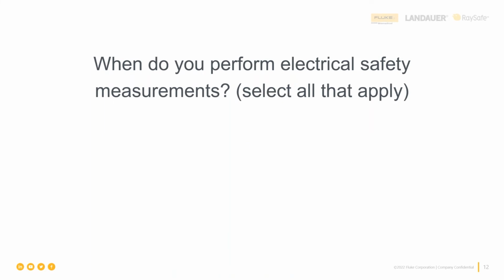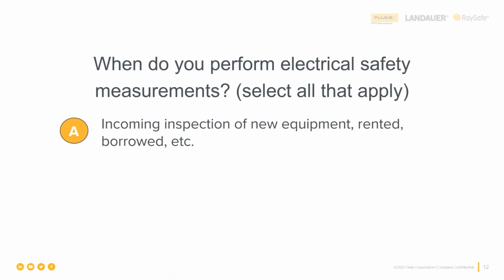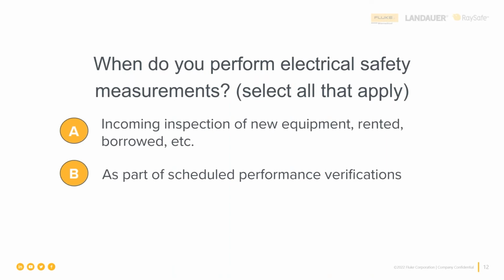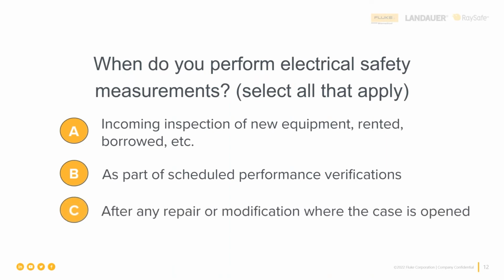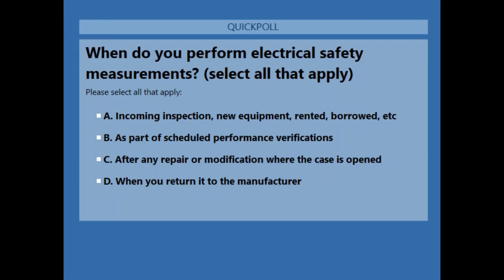So when do you perform electrical safety measurements? Now, electrical safety testing and electrical safety measurements may be different. We'll talk about that under NFPA 99. But when do you perform electrical safety measurements? Incoming inspection of new equipment, as part of scheduled performance verifications, or after any repair or modification where the chassis is opened. And this is multiple response, so you can pick more than one here. So please, Edna, launch this poll question. And that poll question has been launched, Jerry.